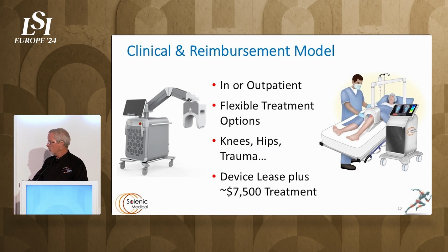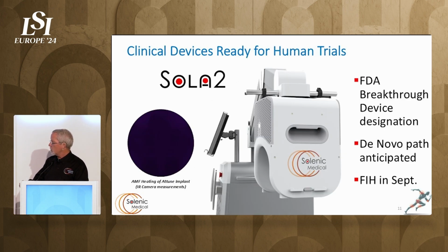This is the device, the initial device called the Sola 2. It's a Sola version A 2,000 watt unit. The knee implant transducer uses about 1,400 watts. A hip implant would be about 1,800 watts, but we'll dial it down for tibial nails, about 800 watts. So using the appropriate dose that can generate that kill is the target.